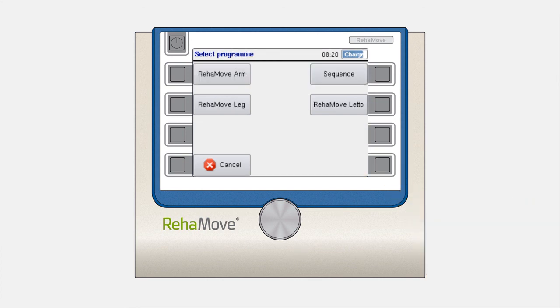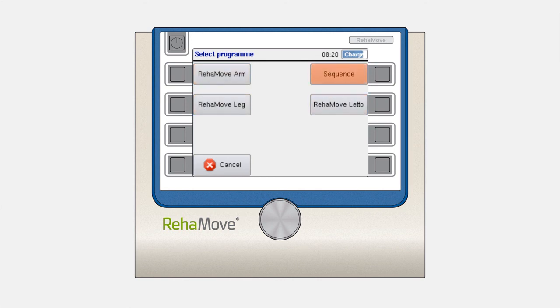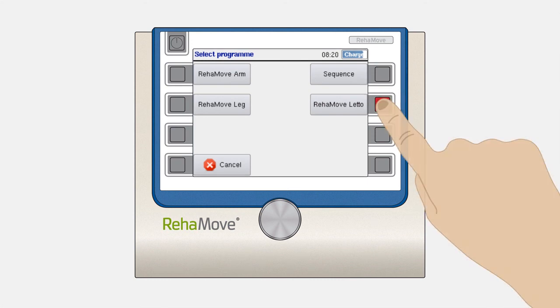The next window will show you your training program options depending on the type of licenses you have purchased. You can choose between the programs RehaMove Arm, RehaMove Leg, RehaMove Letto, and Sequence Training. Programs which are not licensed are greyed out. Choose the program you need with the corresponding button.